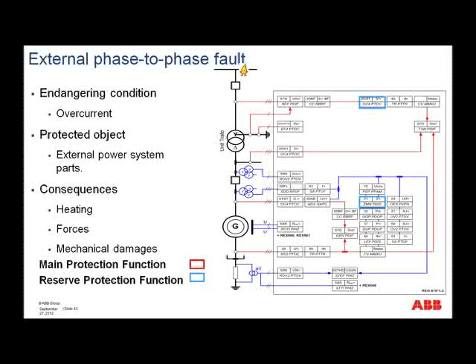If we have this external phase-to-phase fault, we are going to be supplying current from the generator. So it's outside the zone of any of the differential protections. What do we have then to see this? Of course, the underimpedance and the phase overcurrent. But remember, if that is pure phase overcurrent and not voltage dependent, it may not really be able to do the job after the required time delay. So this is for an external phase-to-phase fault.